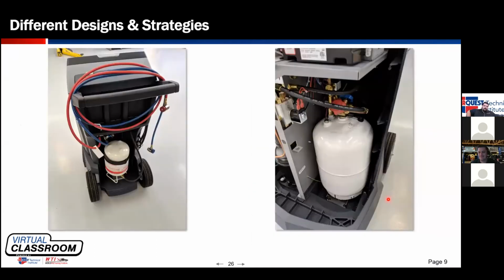Some slight differences between machines. Many of the machines have just the internal tank. Some machines, like this Robinair machine, have onboard storage for a virgin tank of refrigerant. What's nice about this machine is you can set the level of refrigerant that you want in the onboard tank, and rather than having to remember to refill, the machine will do it for you. Once you get to a certain level, it will refill the internal tank from the onboard virgin tank.